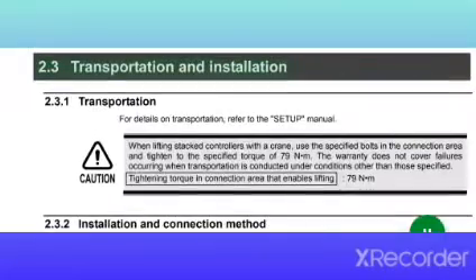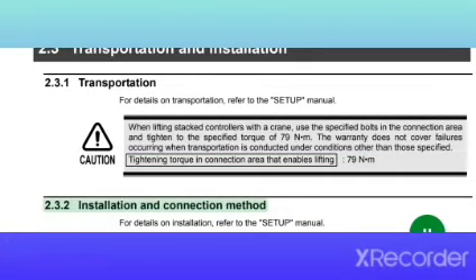2 to 9. 2.3 Transportation and installation. 2.3.1 Transportation. For details on transportation, refer to the setup manual. Caution. When lifting stacked controllers with a crane, use the specified bolts in the connection area and tighten to the specified torque of 79 Nm. The warranty does not cover failures occurring when transportation is conducted under conditions other than those specified. Tightening torque in connection area that enables lifting: 79 Nm.